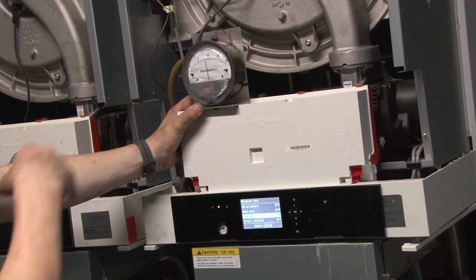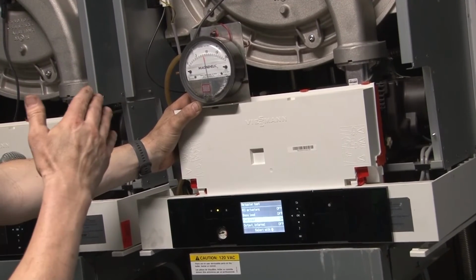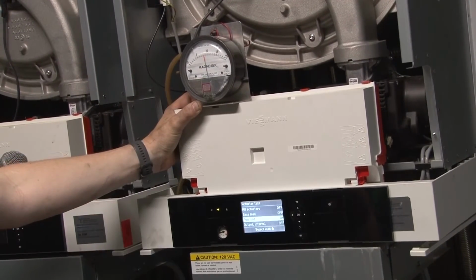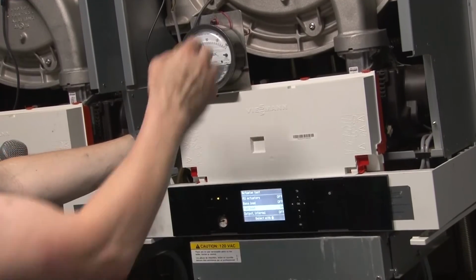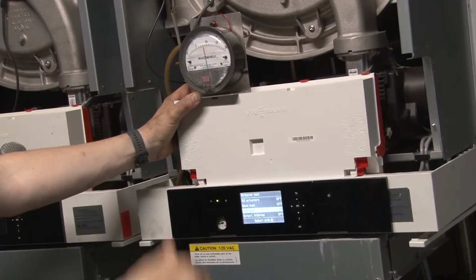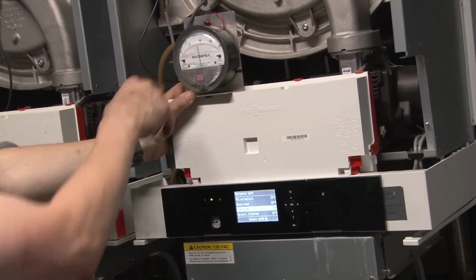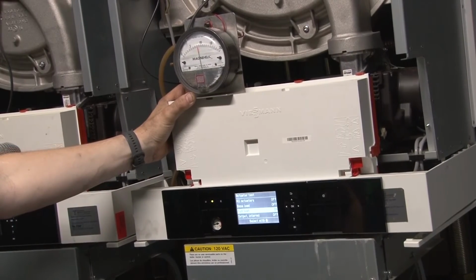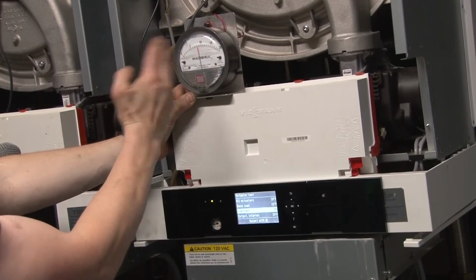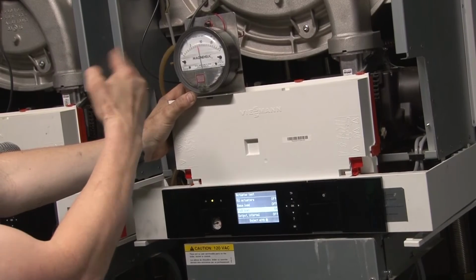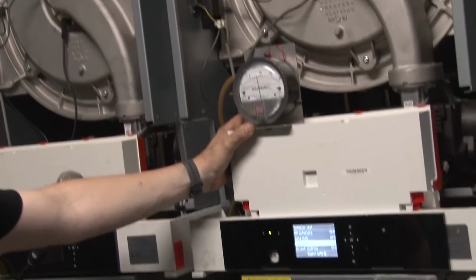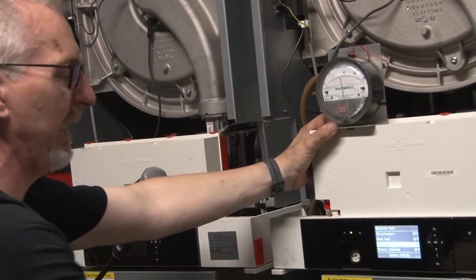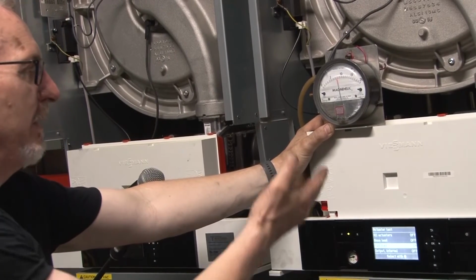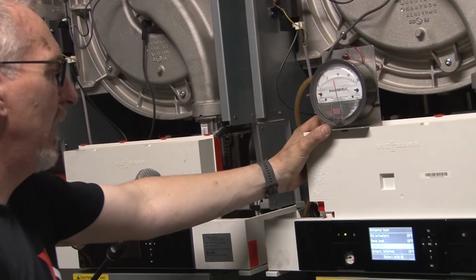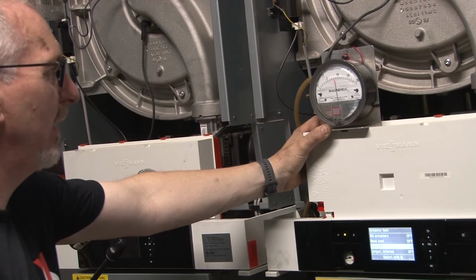This boiler is doing a calibration right now. So basically, I can tell by the fan speed, it's doing a burner calibration, so it's checking the flame signal, doing some referencing here. And you can see how stable that gas pressure is. That's what you want to see. I don't want to see a lot of fluctuation there. If that's fluctuating during this particular process, it usually will end up in some sort of an ignition fault. The burner wants a nice stable function here.